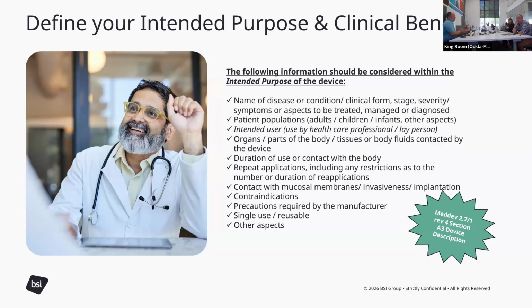if you don't have data for a specific patient group. You also need to consider intended users, especially a lot of our in vitro diagnostic devices. They're actually used by the patients themselves. So you need to consider who's using the device, what part of the body is it touching, duration of use.